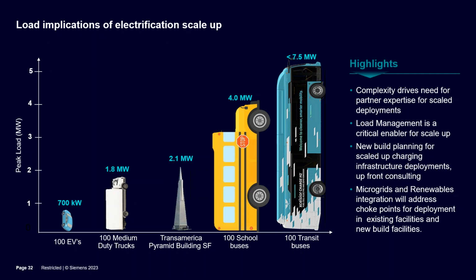I like this slide. It's a good illustration of the implications for electric load of electrifying transportation. If we take the Transamerica building in the middle as our baseline, that's just over 2 megawatts of peak load. With 100 electric vehicles, we add about a third of that, 700 kW - not so bad. With 100 medium duty trucks, it's pretty close to one Transamerica building. But with real transit, 100 school buses brings the equivalent peak load of 2 Transamerica buildings, and 100 transit buses brings us to the peak demand of 4 Transamerica buildings.